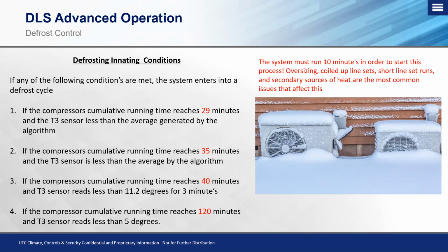Oversizing, coiled up line sets, and what I mean by coiled up is vertically coiled, which essentially creates a cap tube or an oil trap. Now, if they're horizontally done, that's perfectly fine. But vertical becomes the issue, because you can create a pressure drop, like a trap, or like a capillary tube, excuse me. And then you can also have an oil trap as well with that vertical coiled up line set. Short line set runs, so minimum line set on a ductless is 10 foot. Issues with short line sets is that you can flood the condenser, and essentially it'll cause frosting of the condenser itself. So we have to maintain that minimum of 10 foot.